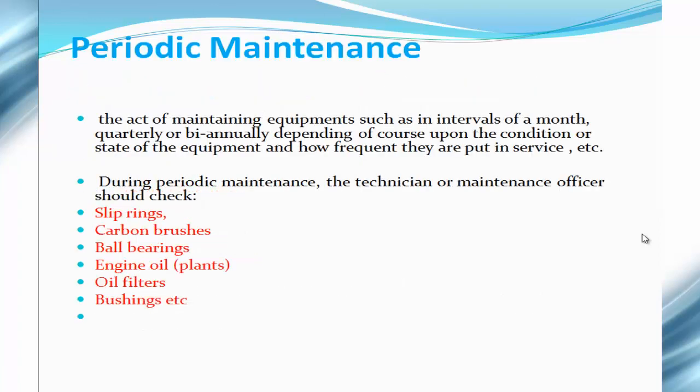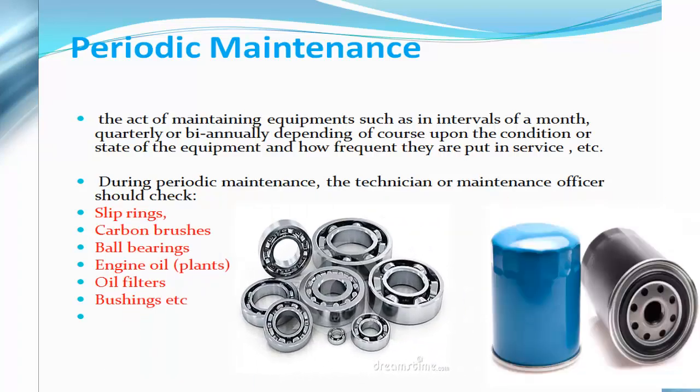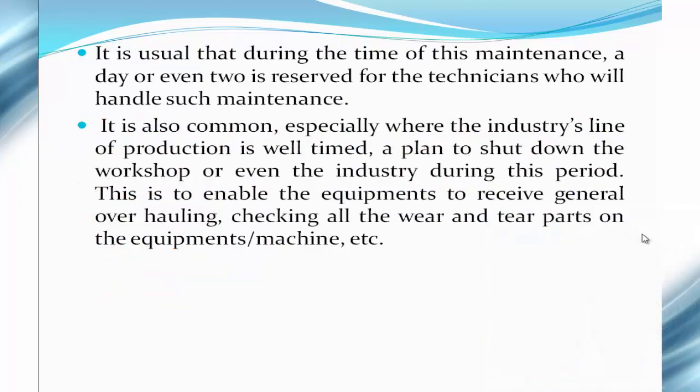The periodic maintenance is the type of maintenance carried out on a periodic basis — not daily, but at intervals of a month, biannually, or quarterly, depending on the condition of the equipment and how frequently it is put into service. During periodic maintenance, the technician is expected to thoroughly check items like slip rings, carbon brushes, ball bearings, engine oil plants, oil filters, bushings, and so on. A day or two is usually reserved for the maintenance officers handling such maintenance.